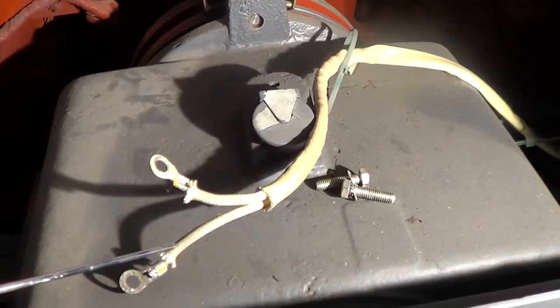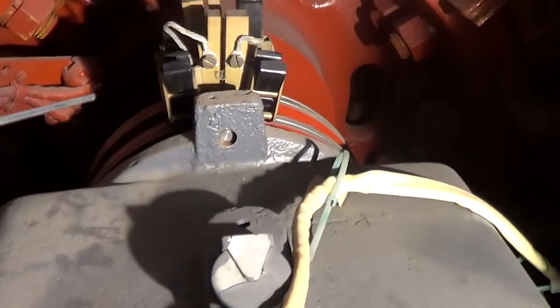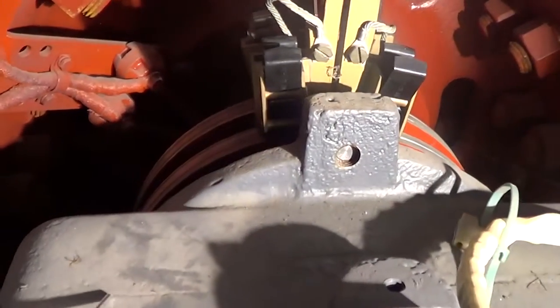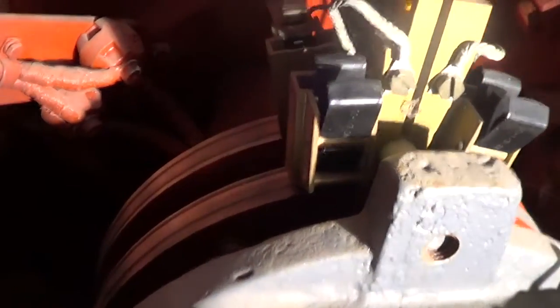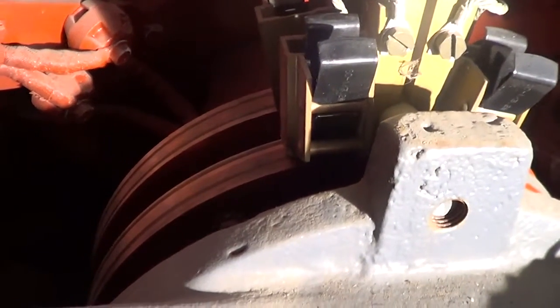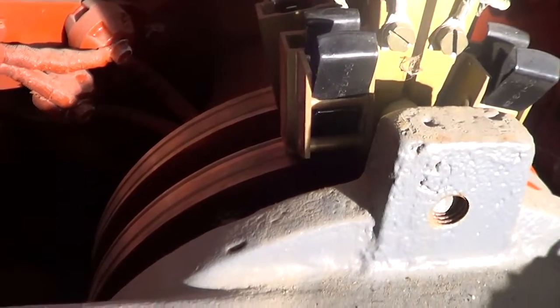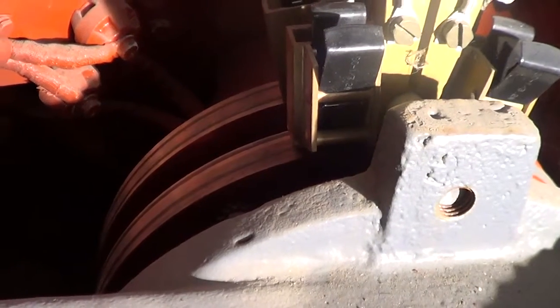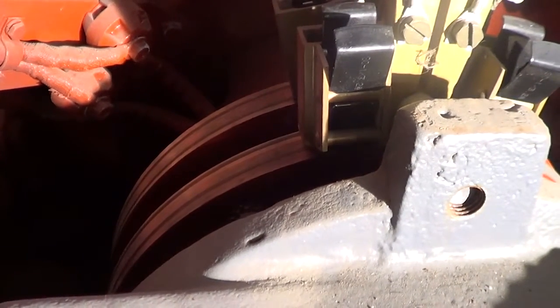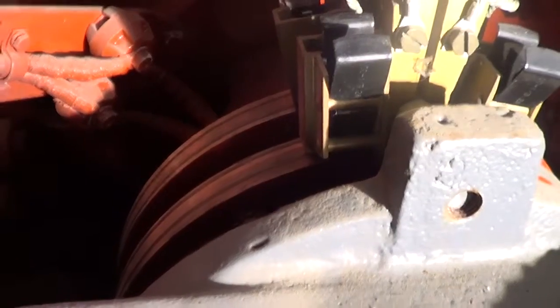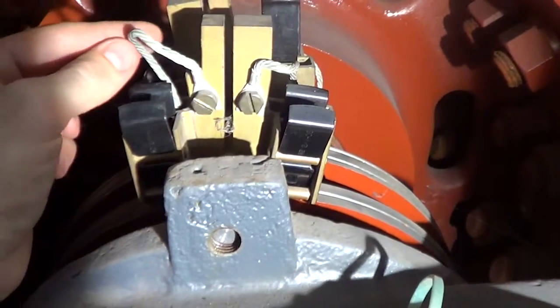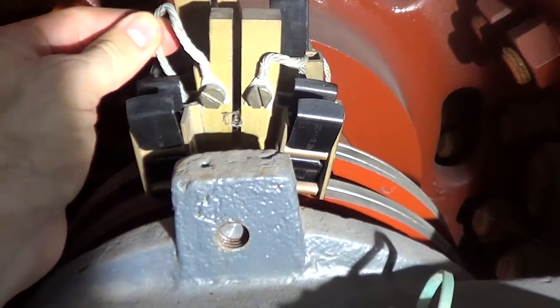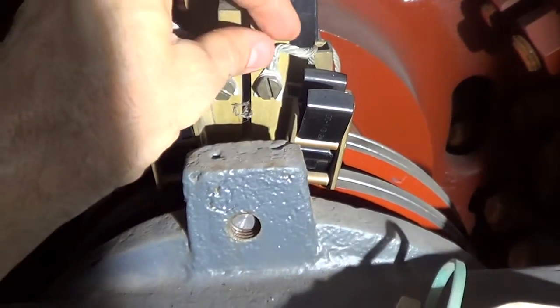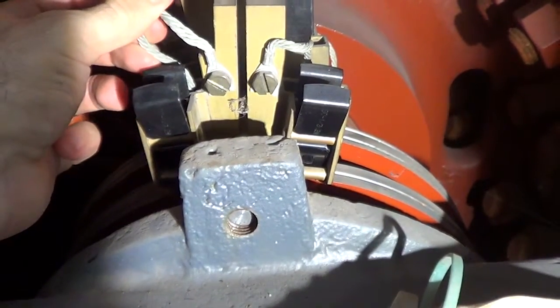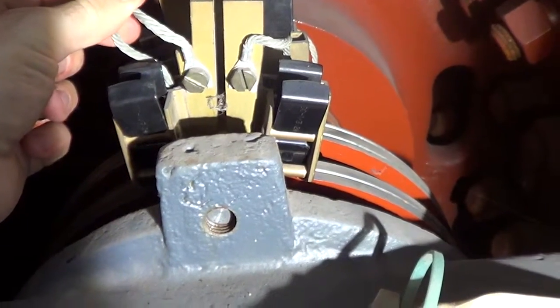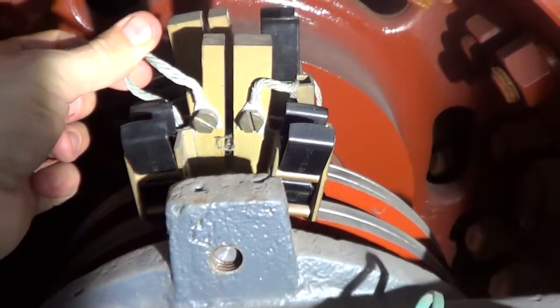You can see that the main field leads have been disconnected from this set of collector rings, and now it's time to inspect the rings. Visually inspect the ring and ensure that there is a reasonable carbon film and no evidence of gouges or other defects. Take careful photographic measurements and inspect all around the rings. Check the spring tension on each of the brushes by pulling on the pigtail and ensure that the tension is the same. Use a spring tensioner if possible to get an accurate measurement and record this in the report.